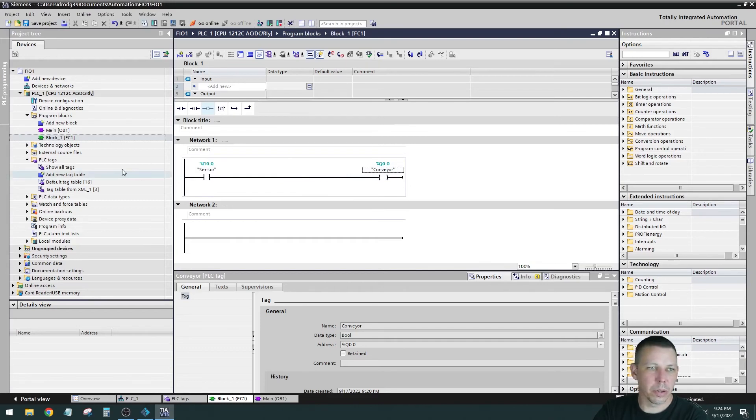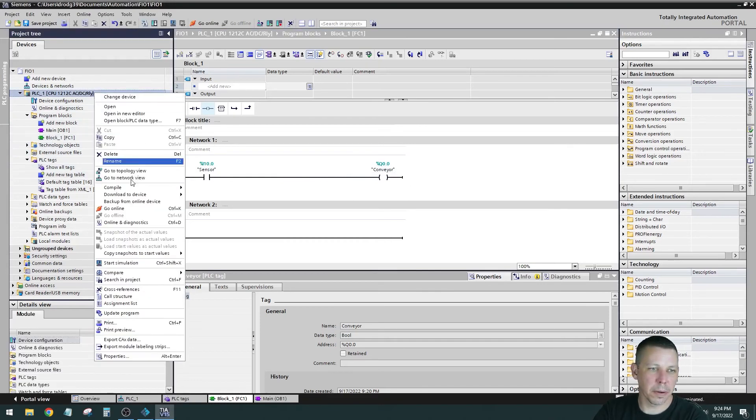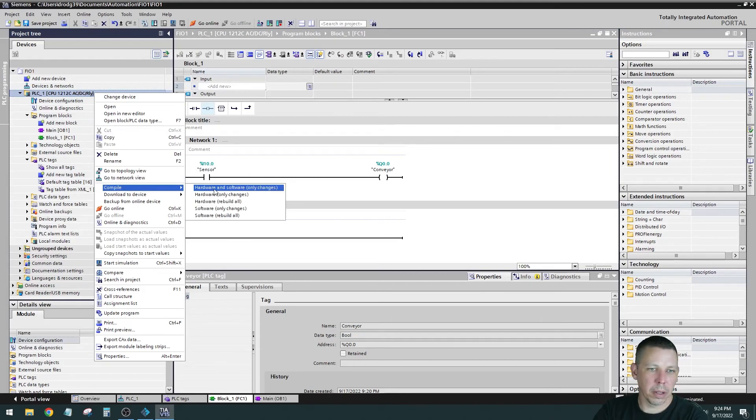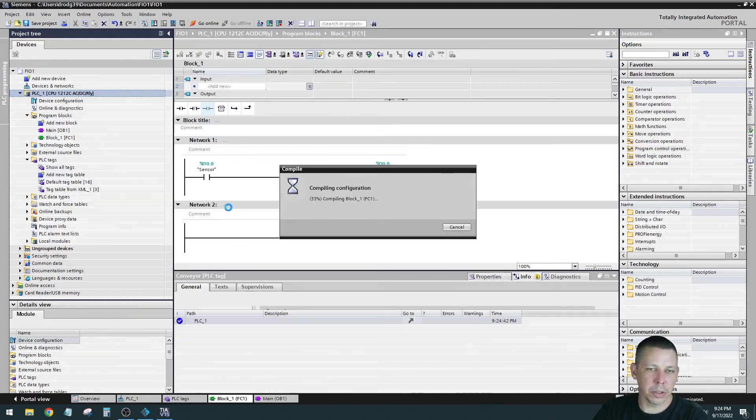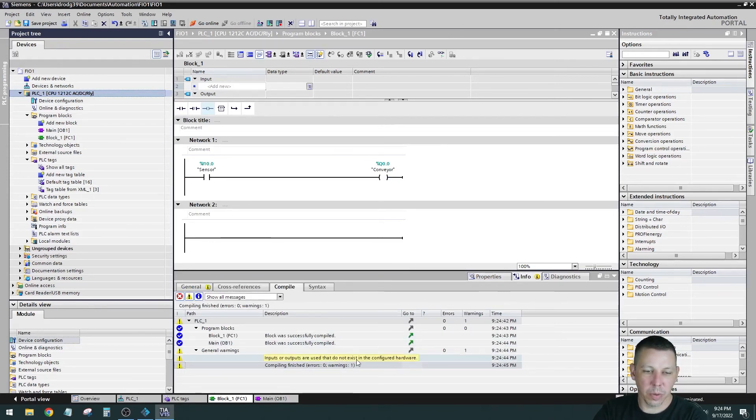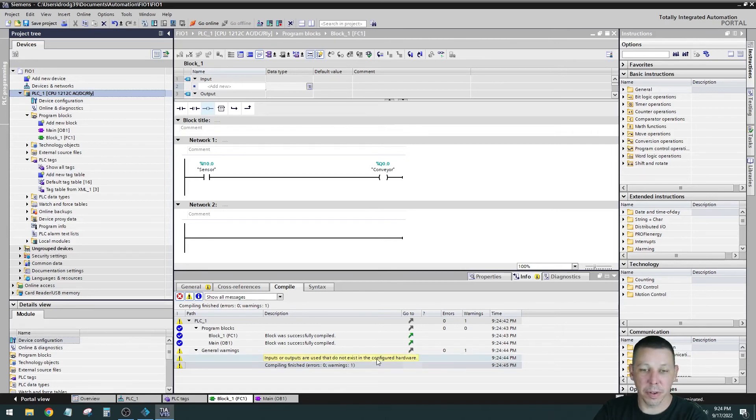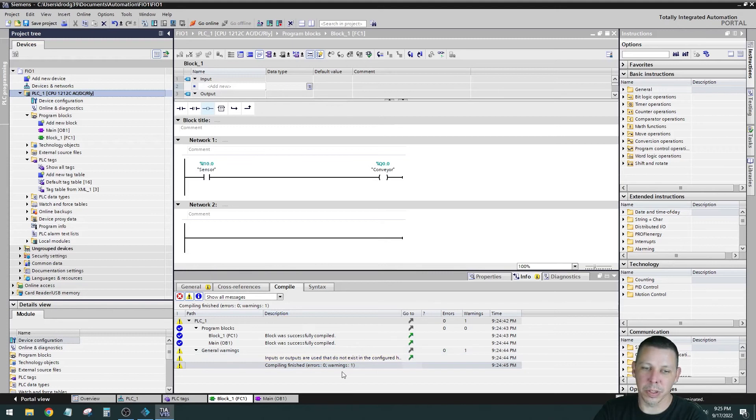So now we have OB1 calling our function one. In function one, we have our normally open sensor. It's normally open because when you look at it, you can see that it is true right now because it's lit up. That's why we want a normally open instead of normally closed because we want this to allow the conveyor to run until that sensor is broken. So let me compile this and you right click on the processor and compile and software only changes. And we got one warning. The warning that we got is inputs or outputs are used that do not exist in the configured hardware, which is true because we set that offset. So there is no input 10 on this processor. It's just a warning though. So we can still download it.